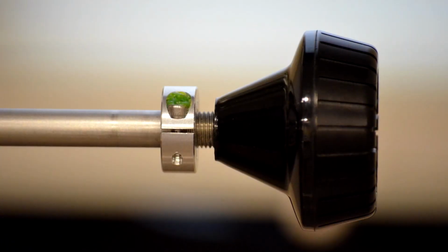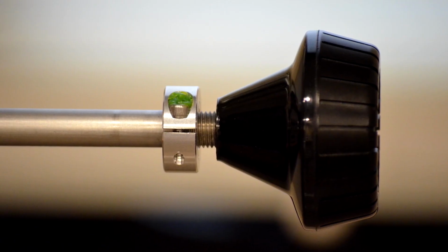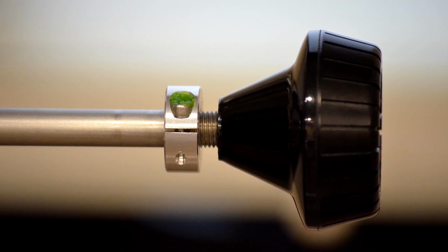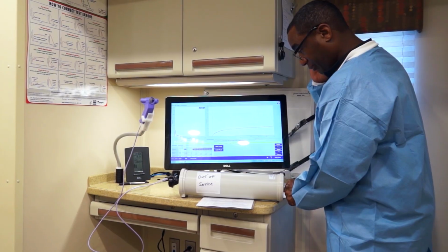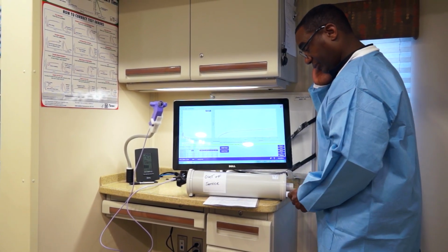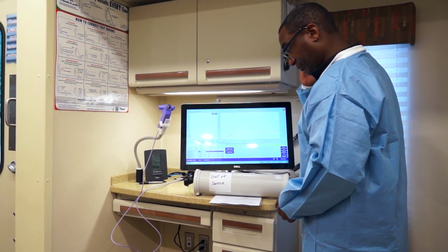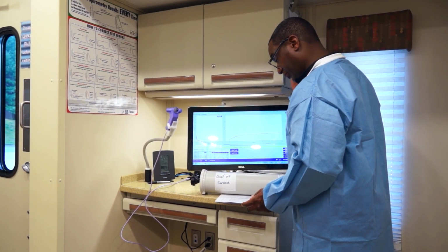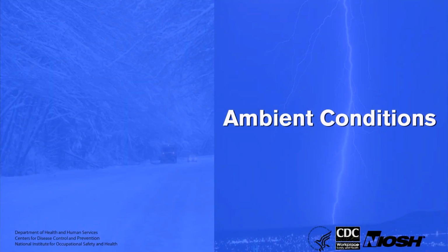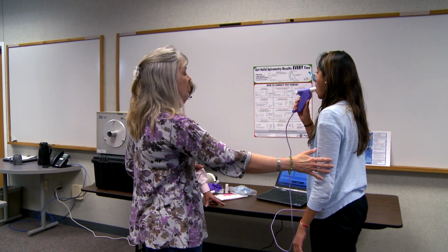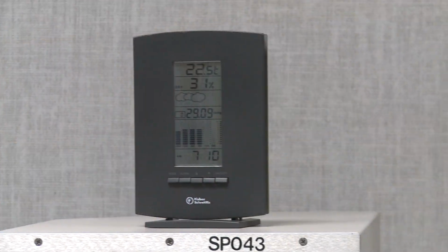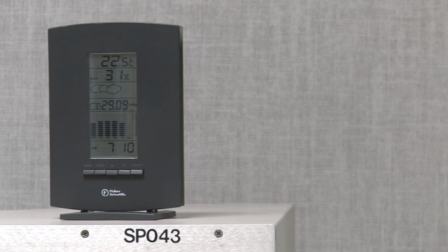If the adjustable ring stops along the plunger are loose or have been moved, or if the syringe is visibly damaged, it must be considered out of service until it is recalibrated by the manufacturer. Air in the lungs is at a different temperature than the exhaled air measured by a spirometer. This can affect measured expiratory volumes. Therefore, it is necessary to correct for these temperature differences.